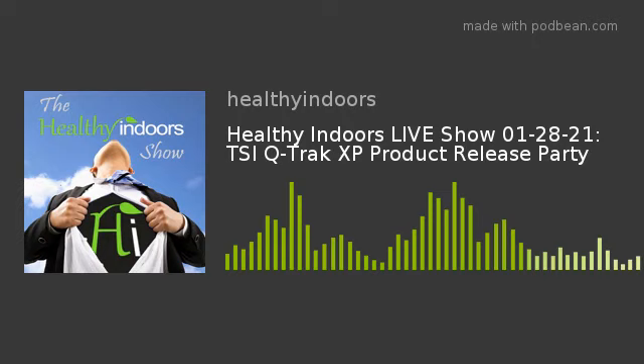If you send in your old Q-Trak or any of our other TSI devices, we'll take it out of the box, put it in our test fixtures, and run an as-found test. How is it performing right now, before we make any adjustments? That gives you even more confidence. For products like our VelociCalcs, when you're doing critical space testing, pharmaceuticals, laboratories, clean rooms, it's imperative that the data you get is accurate and trustworthy, and that's where that as-found data comes in.